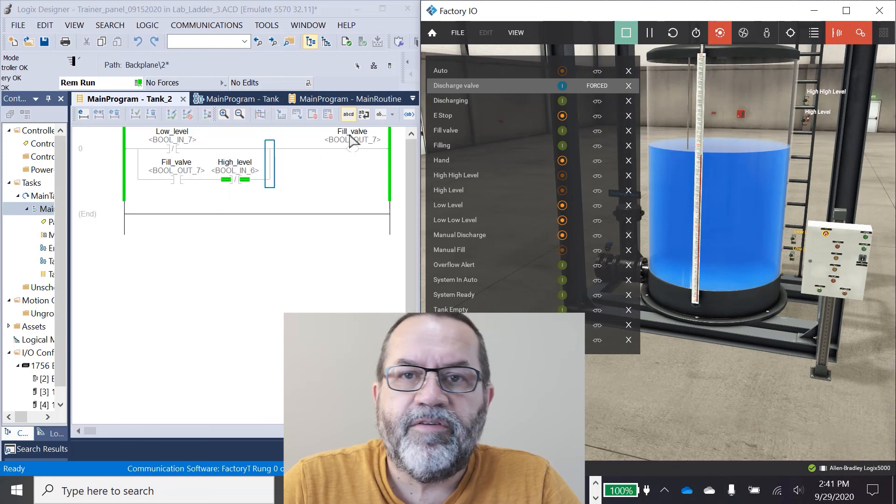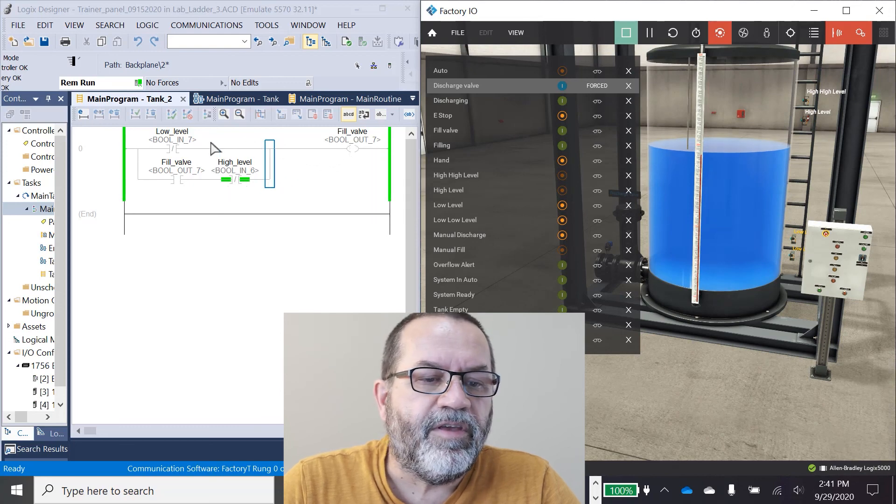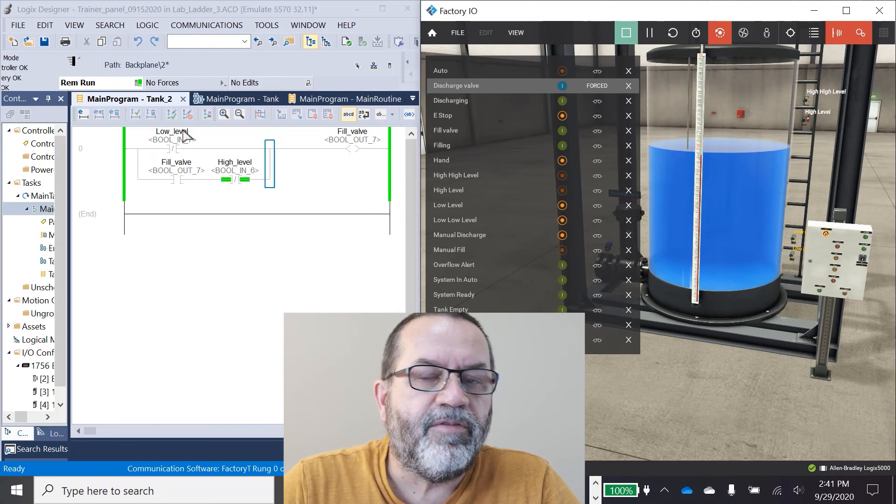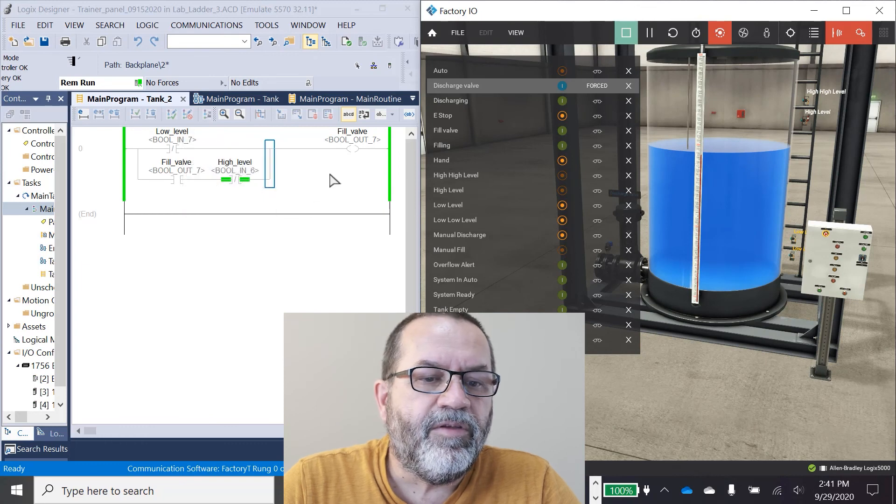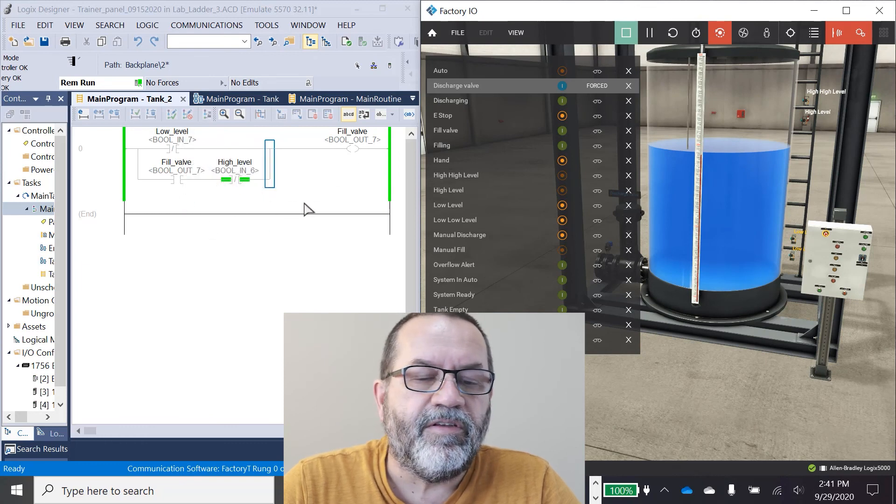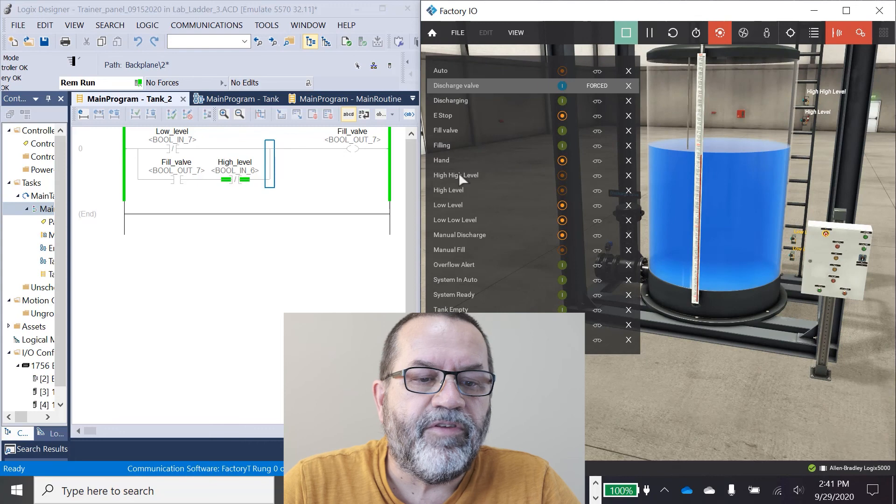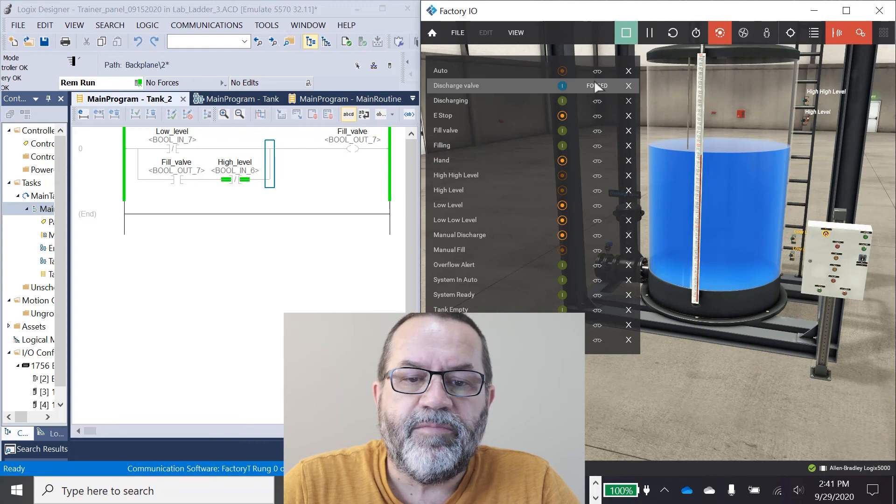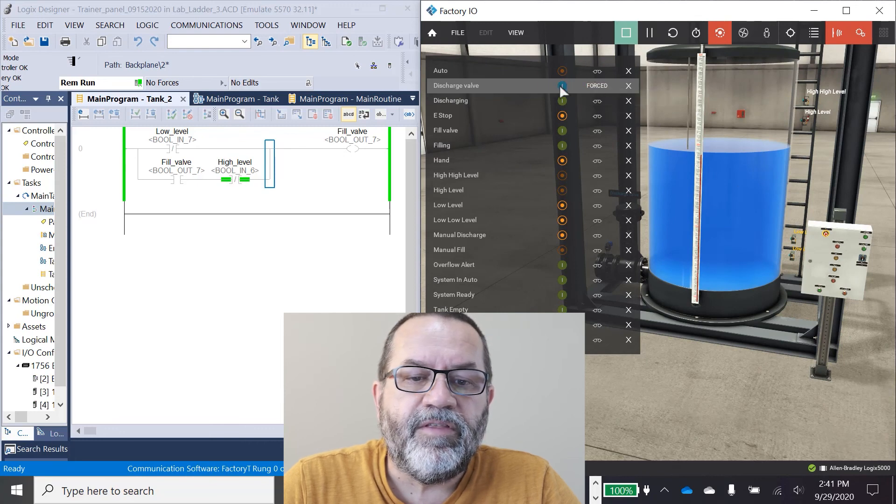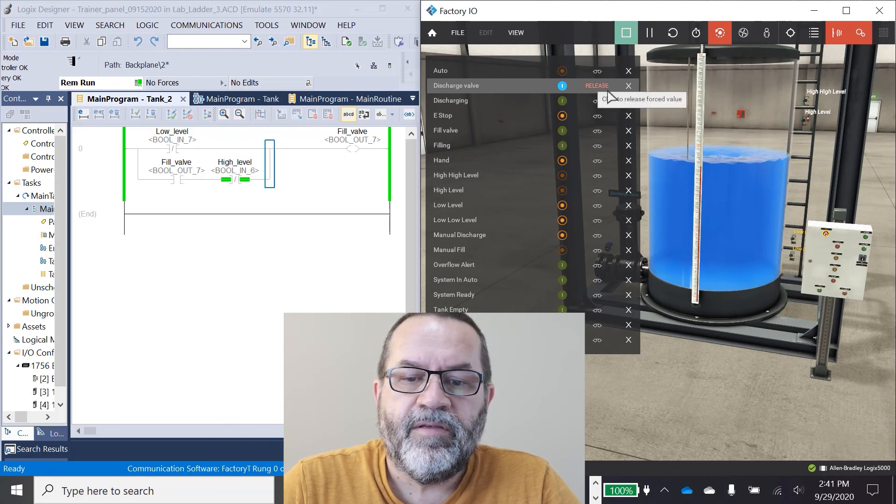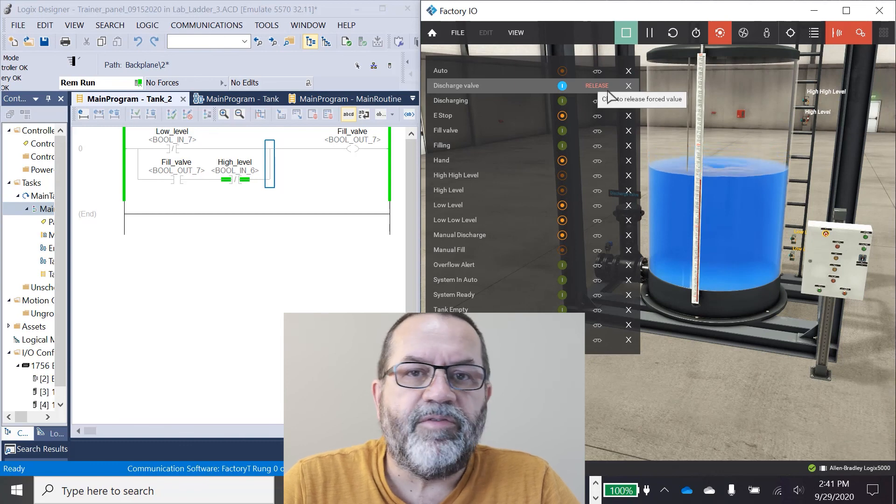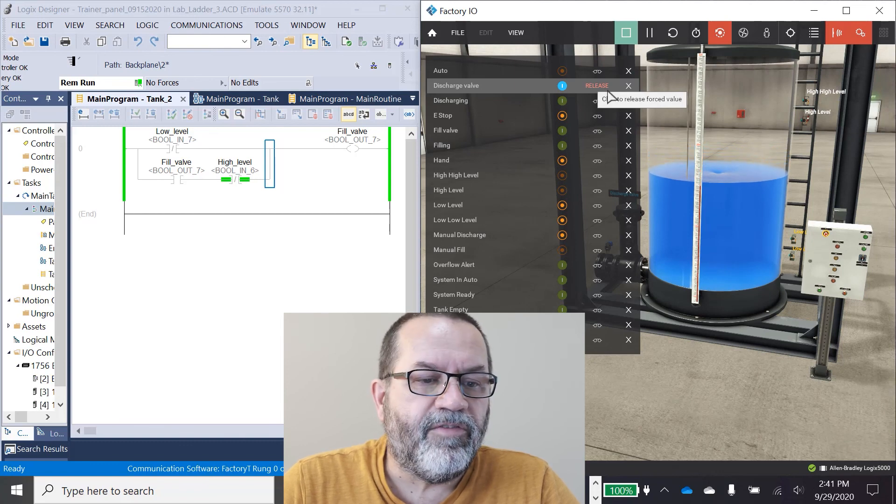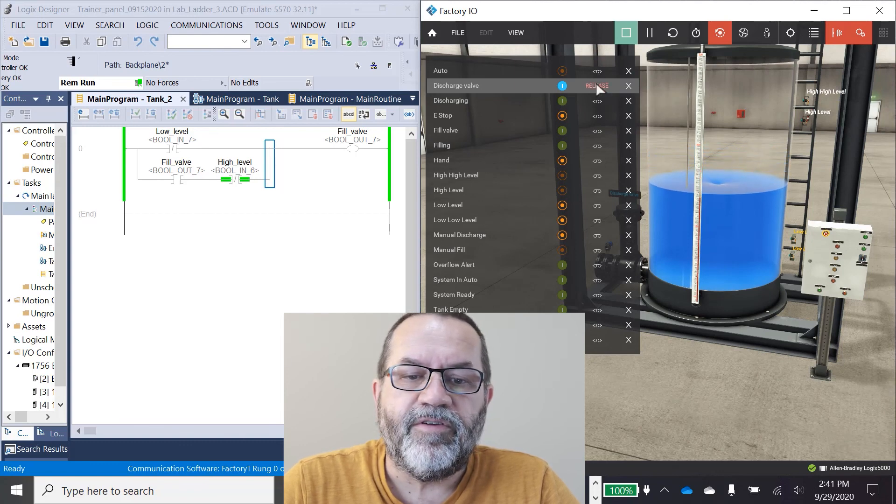But it's not starting that fill valve because I need to get all the way down to the low level sensor to start this seal-in again before it will seal itself in. So I'm just going to drain this down until I get the low level sensor, and then we'll watch it go again.